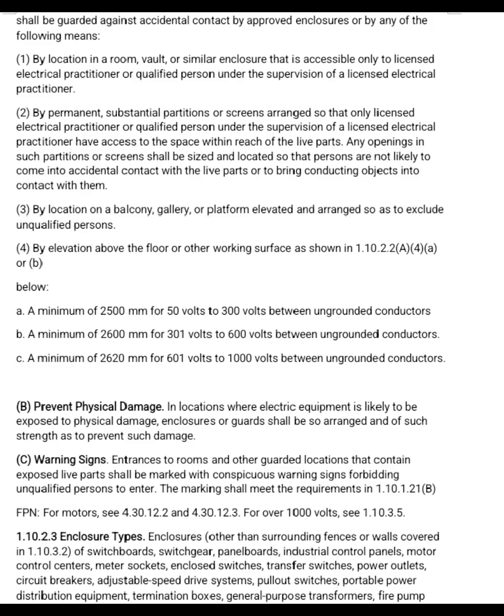Number 3. By location on a balcony, gallery, or platform elevated and arranged so as to exclude unqualified persons. Number 4. By elevation above the floor or other working surface as shown in 1.10.2.2 A 4 A or B below. A. A minimum of 2500 mm for 50 volts to 300 volts between ungrounded conductors. B. A minimum of 2600 mm for 301 volts to 600 volts between ungrounded conductors. C. A minimum of 2620 mm for 601 volts to 1000 volts between ungrounded conductors.